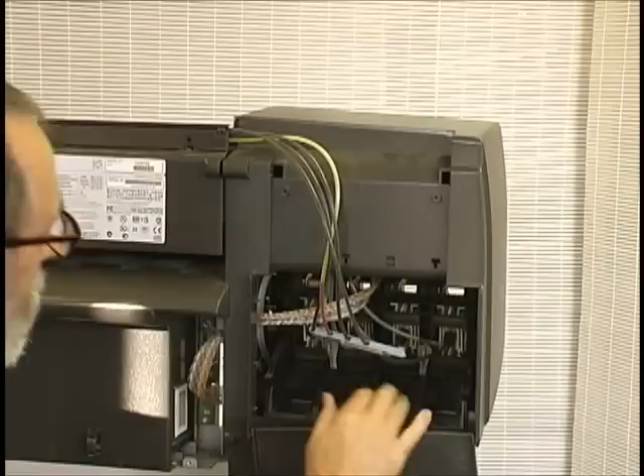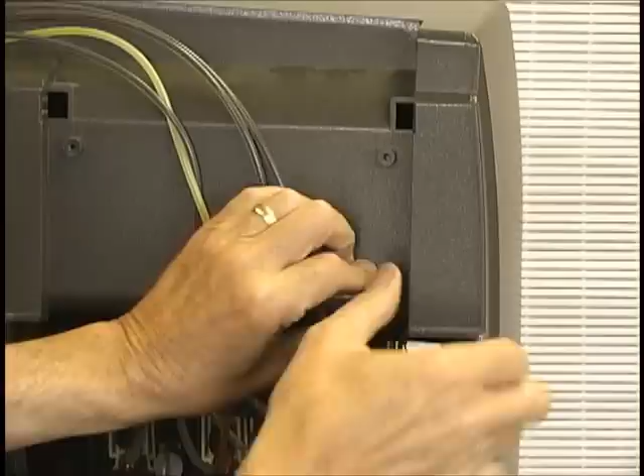Okay, I've turned the machine around so I can make it easier for you to see how to get this back in. These pieces right here go on these tracks right here. Don't want to trap the cable back there. You push that in part way, and then I'm going to reconnect the ribbon cable on the blue connector and the air pressure tube goes back on the air pressure connector right here. Okay, push it forward so we can latch these. It should go right into the slots and latch fairly easily. And that's it. And then we're going to reattach the anchor here on the frame. Just like that. And it's good to go.